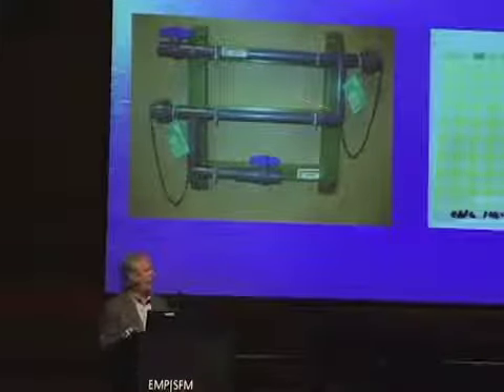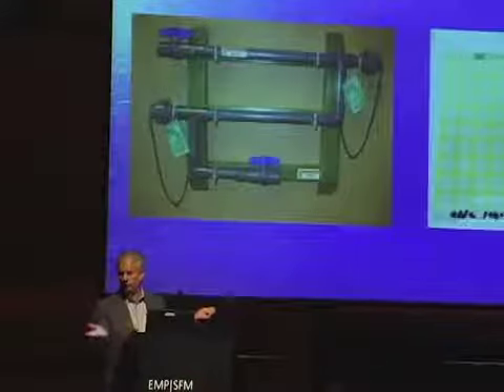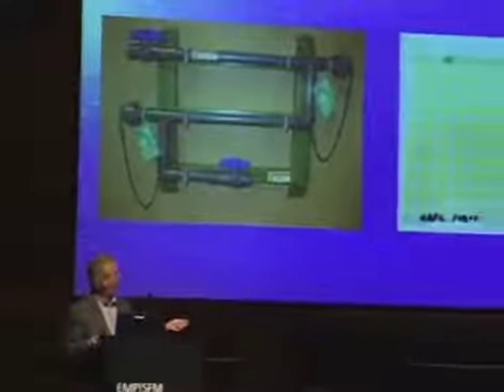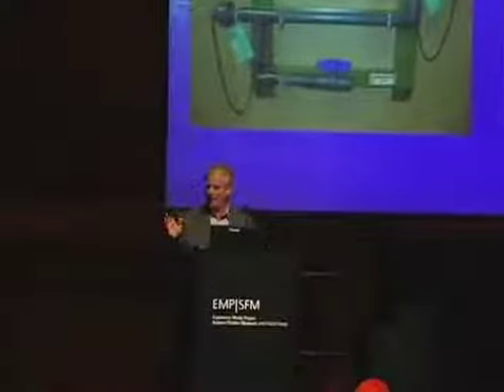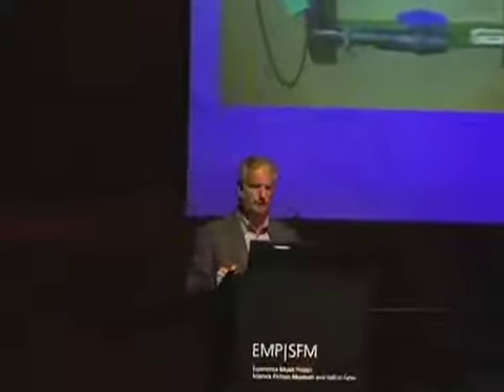We have the monitoring ability. We have corrosion coupon racks, so you can monitor corrosion rates. We have the biological dip slides in the field. You also have lab backup capabilities, so you can go to any lab and have things analyzed for mass balances and everything else. So you have the ability to monitor these programs, and we normally give them about a 90-day window.